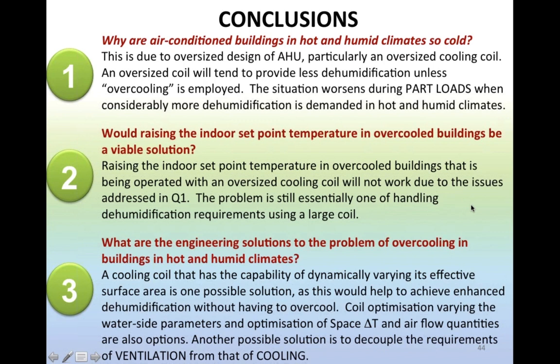What are the solutions that we can resort to? Well, we can look at a dynamically varying surface area of the cooling coil, which would allow us to literally customize the coil size, the effective surface area of the coil, to what the cooling loads might be in the building, in the space, as it goes through its dynamic range of operation. We have done other studies, which are not part of what I'm going to be talking about in this talk anyway. Then we said, why don't we look at decoupling the ventilation requirements from cooling?